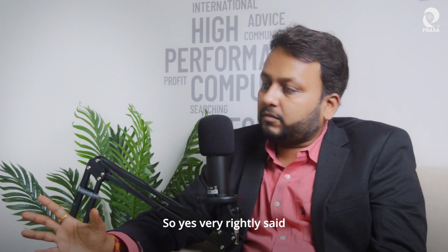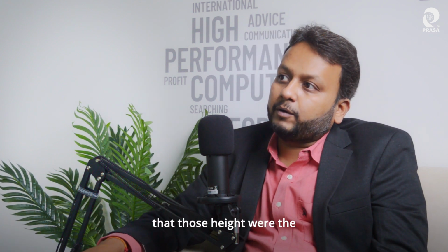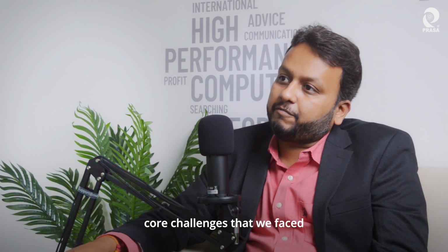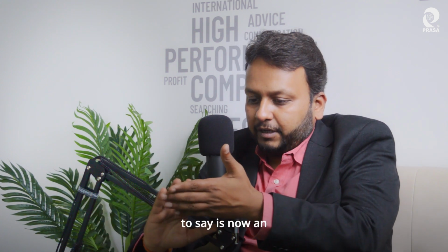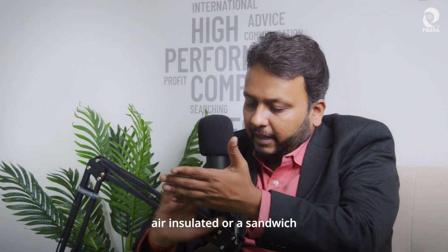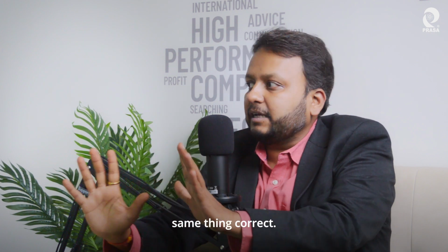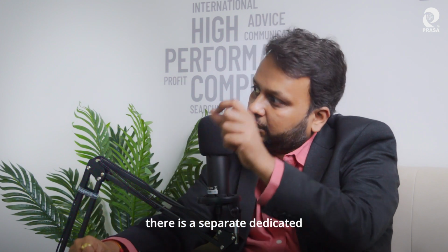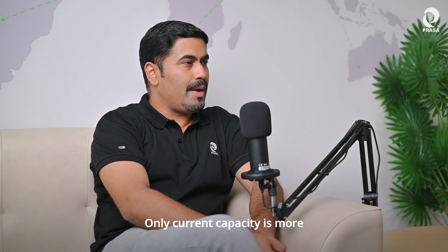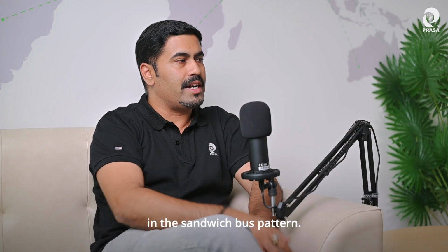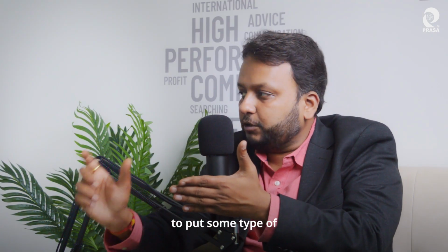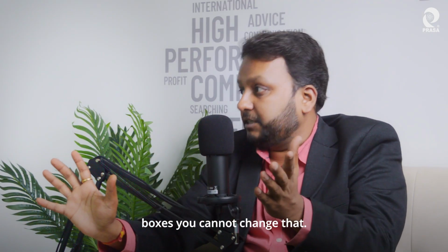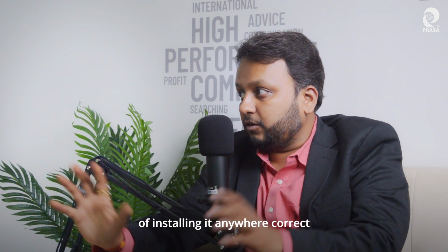Correct. So yes, very rightly said that height was the core challenge that we faced, and that's how we mitigated it. So what you are trying to say is, air insulated and sandwich are more or less the same thing. Correct. Only air insulated has air as insulation. In sandwich, there is separate dedicated insulation. Only the current carrying capacity is more in the sandwich busbar. However, the limitation is that at a fixed interval, you have to put some tap-up boxes. You cannot change that. You don't have the flexibility of installing it anywhere.